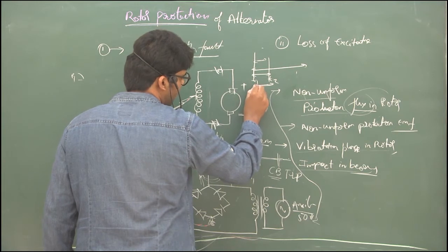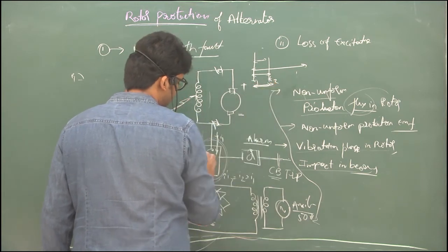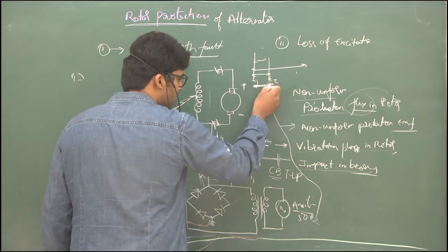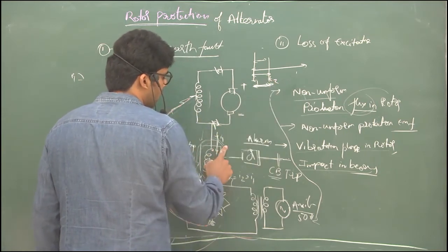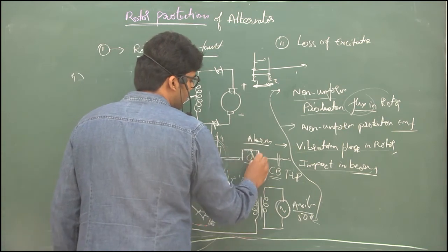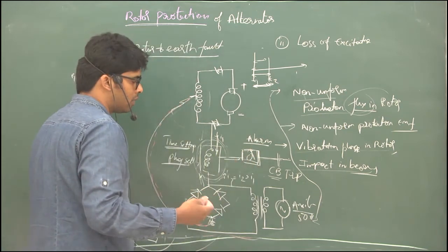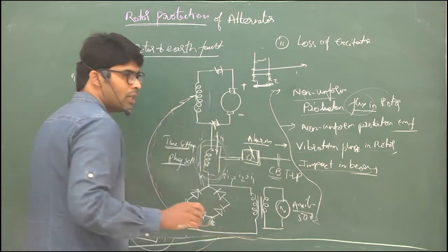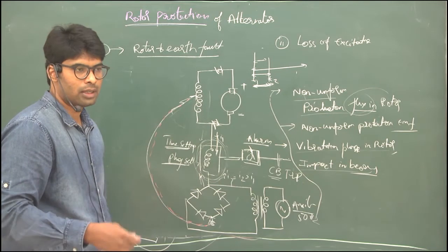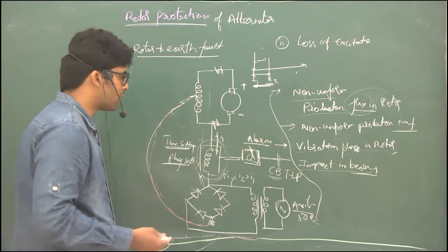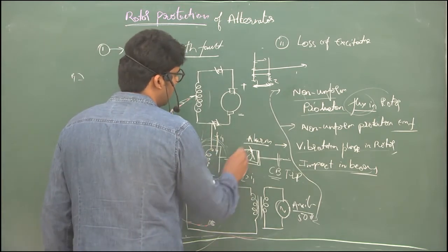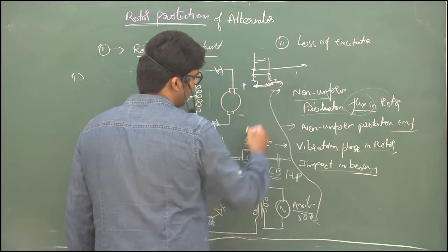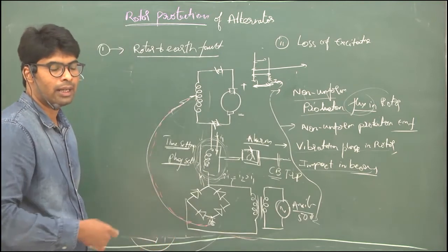So when the fault occurs, the relay will check the trip setting time and plug setting in the relay coil. If that fault is rectified before the time, it won't operate. At that time, it gives an alarm to the person who is looking at this. He comes and rectifies the fault. If it is sustained up to this time, then only the relay gets operated.